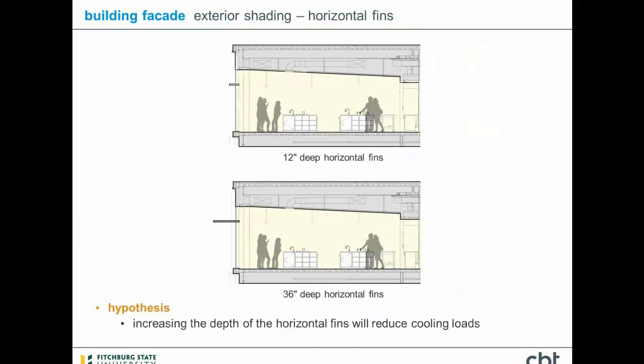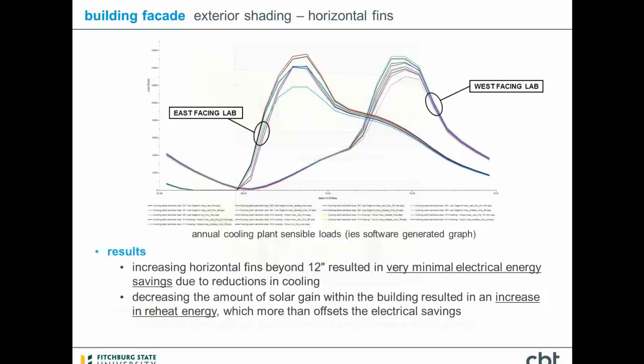And then we looked at a series of vertical and horizontal shades to try to optimize the right performance of them. So looking at what we did, we started with the horizontal shades. We looked at a series of depths. This one is showing the 12-inch and the 36-inch. And the idea being that if we can eliminate some of the unwanted solar gain into the space, we can take some of the load off of the cooling. This graph actually is an amalgamation of all of the studies that we ran with vertical, horizontal, no shades, and maps them all together to really express a major point that is the focus of our goals here.